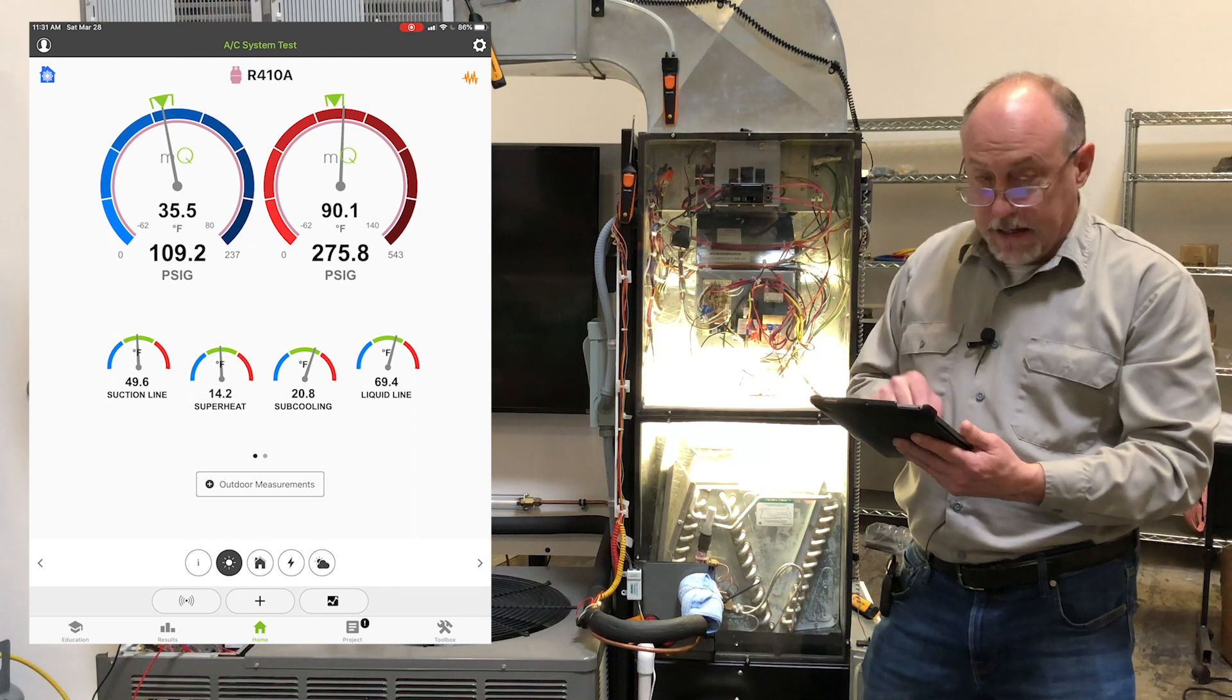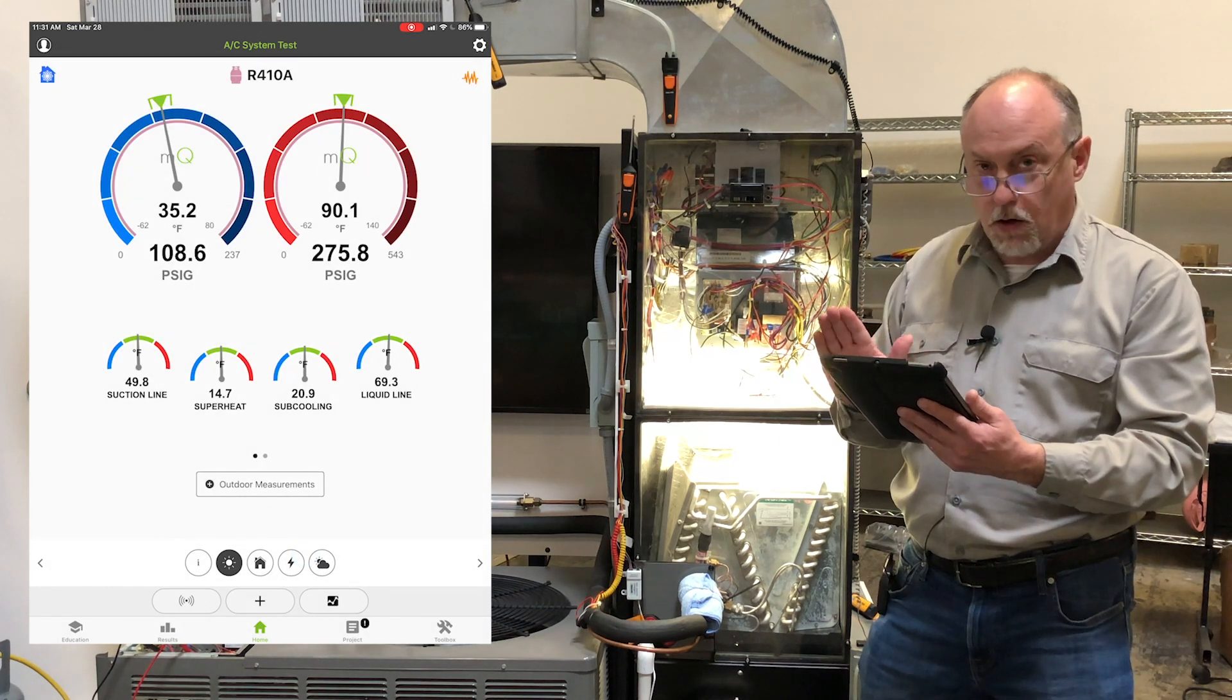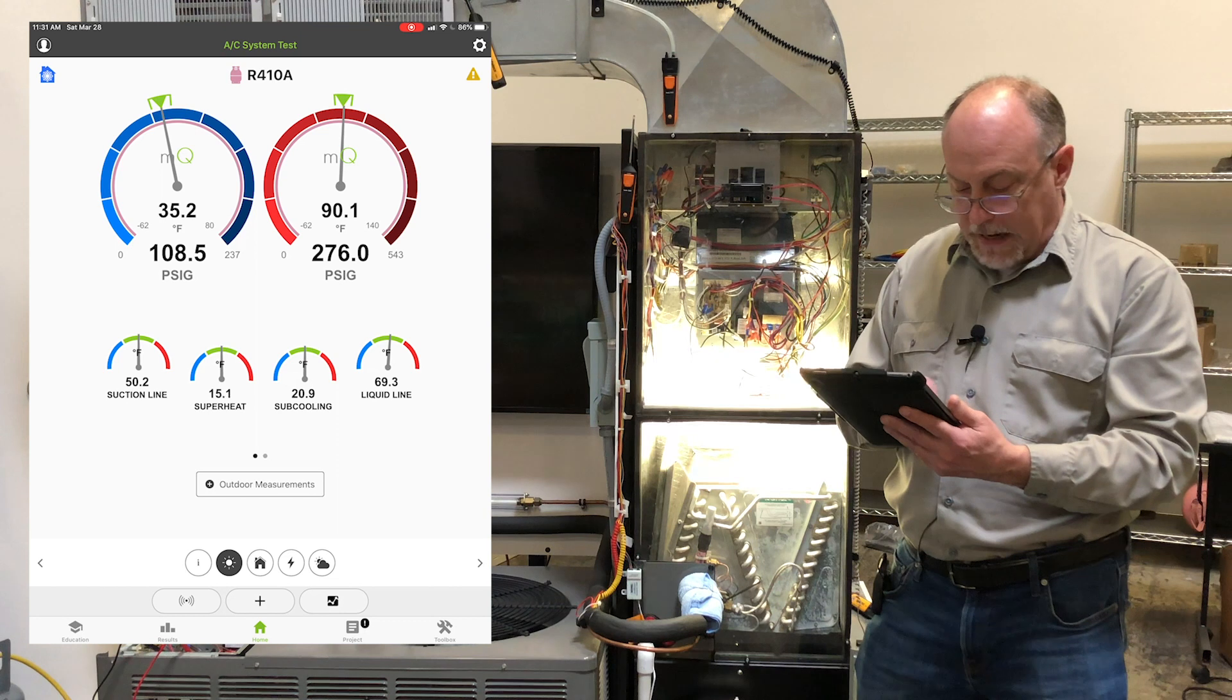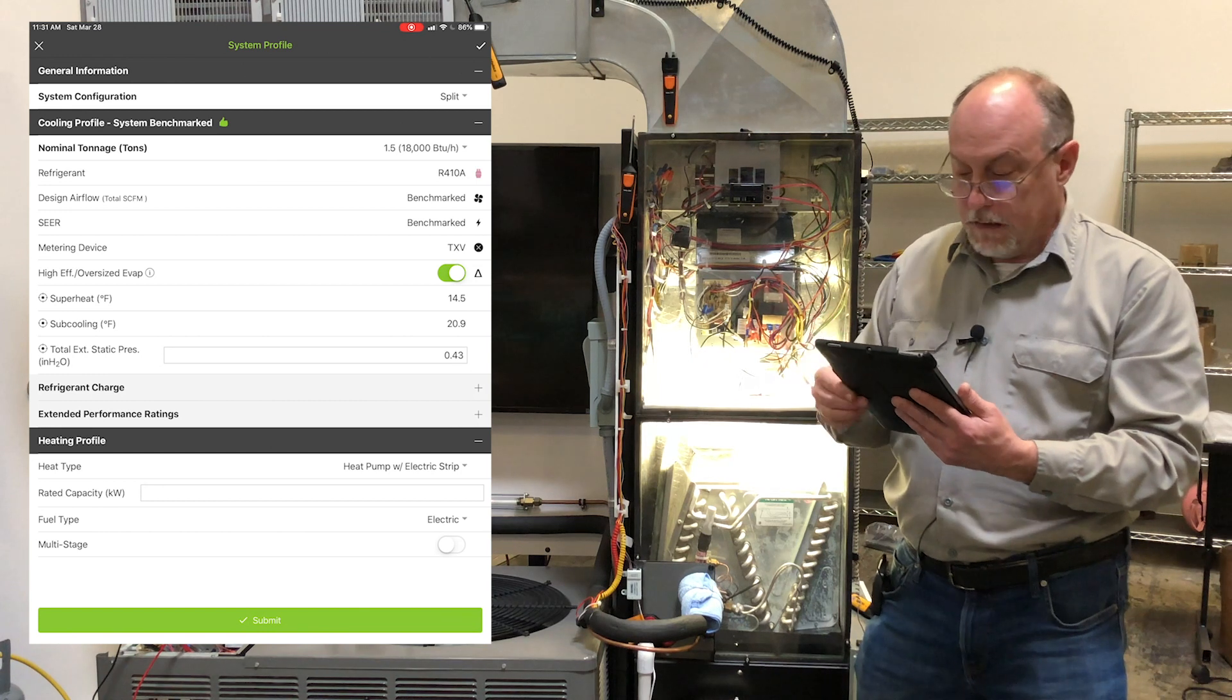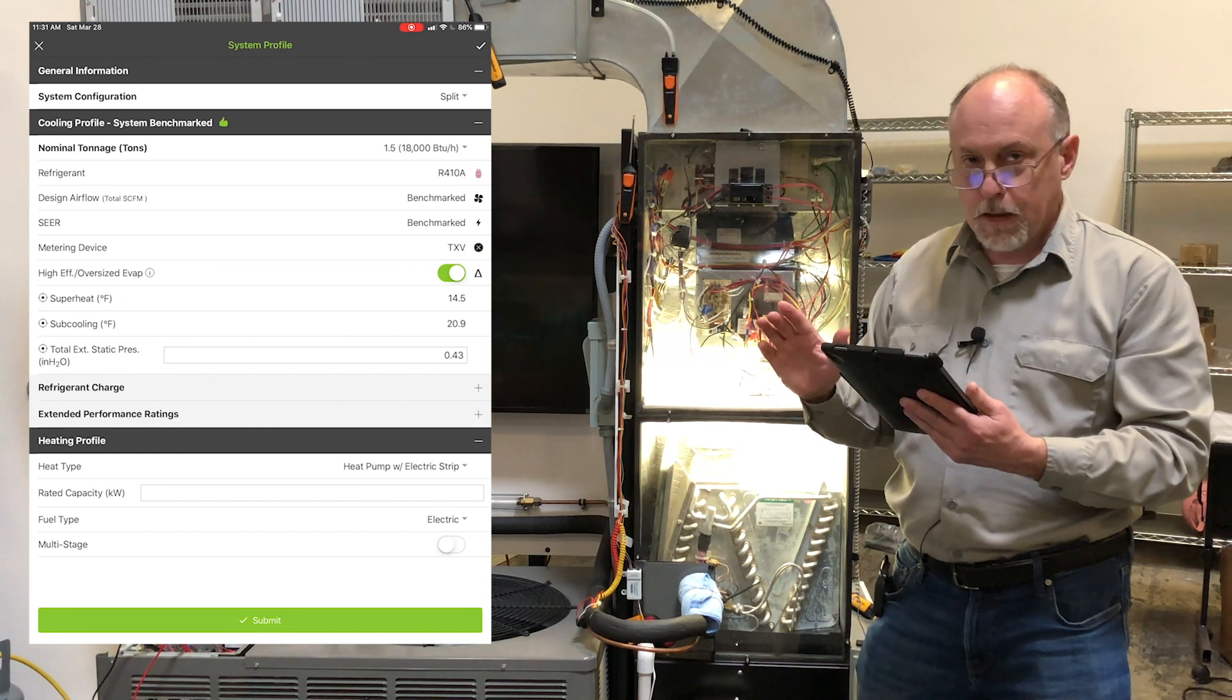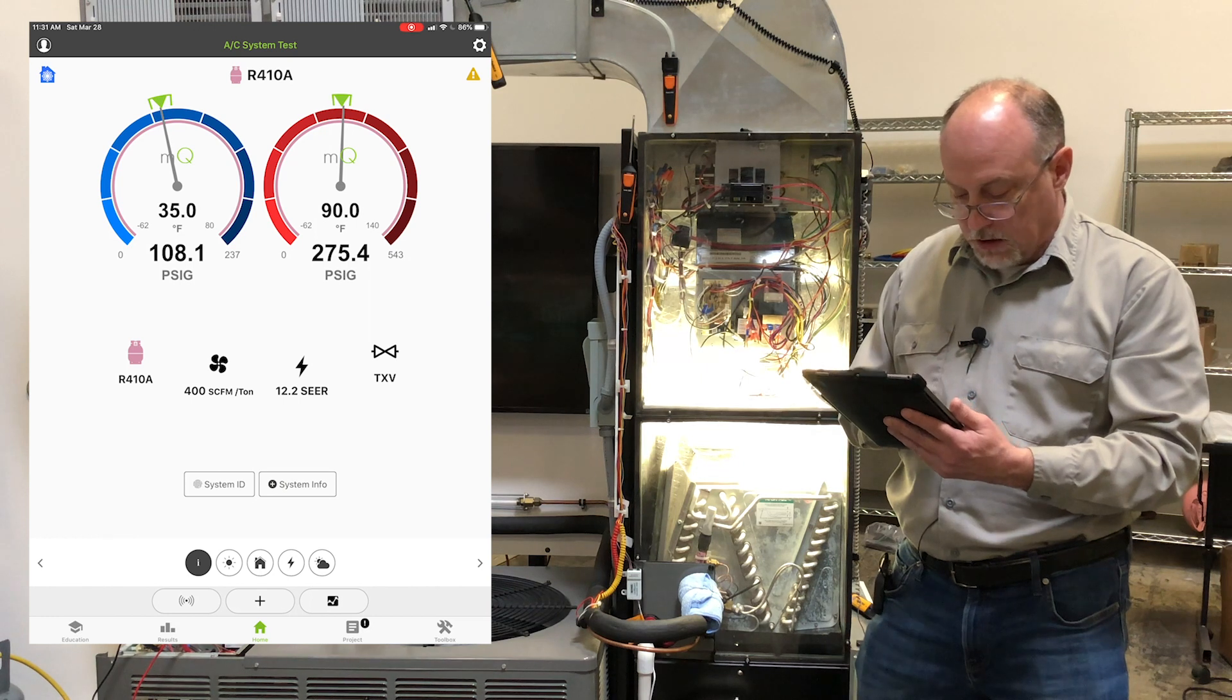I'm going to go ahead and benchmark that. And here's how you benchmark. You hit the plus key on here, and you put set benchmark. Now you'll notice that the targets all lined up. So now my subcooling, my liquid line temperature, my high and my low pressure, all that data lined up. And if I go back into the information now on the system, you'll see that it's benchmarked now at the top. The superheat and the subcooling targets are locked in. My total external static pressure now went from 0.5 to 0.43, that's locked in. So now going forward, when I come back out to diagnose the system, that's where it's going to really help all the technicians.